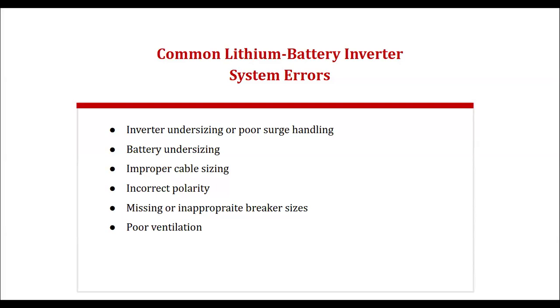So then another one is improper sizing of cable. Many people are fond of saying, if it is 10 kilowatts, just let me use 16 cable. It will charge now. What's the charging current? By the time this battery demands charging current and is saying I need 100 amps, and the inverter is capable of giving it that 100 amps, and you are using a tiny cable, it's going to be eating up. A lot of calculation will be going on through the BMS, trying to manage the battery current, trying to do everything, and the cable will be eating up. When you want to load it, the same thing will be happening.